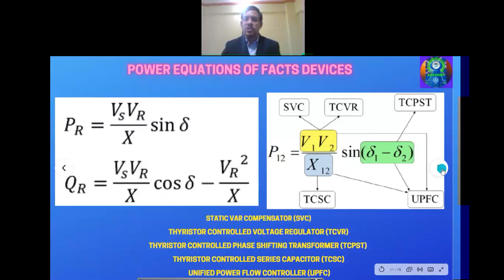The same thing is shown here also, that is how we enhance the power handling capacity, or control the power angle. We know that at 90 degrees we get maximum power output, but we never operate the system at 90 degrees, because there are chances of losing synchronism beyond this. So the safer range is mostly less than 30 degrees. And this is a control system. We have to measure parameters from this power line and feed them to our control system, so that we can adjust the output of these FACTS devices, and accordingly the power system parameters can be adjusted.